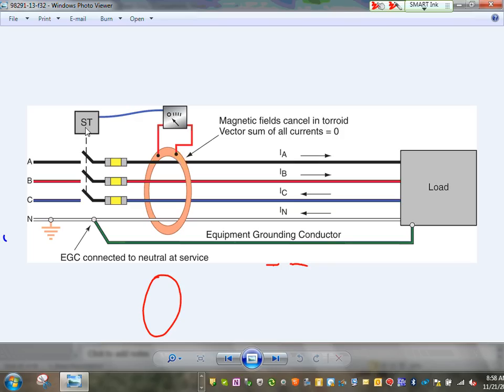Adam, this is only required if your service is 1,000 amps. So if you've never seen it, never heard about it, I don't know if you guys talk too much about it in the construction, 1,000 amp or higher. And the voltage has to be 480/277. If you use 240, 120, nah. If you use 208, 120, don't think about it. It's not required. So that's on a higher level, that's what we do in the industrial project next time.